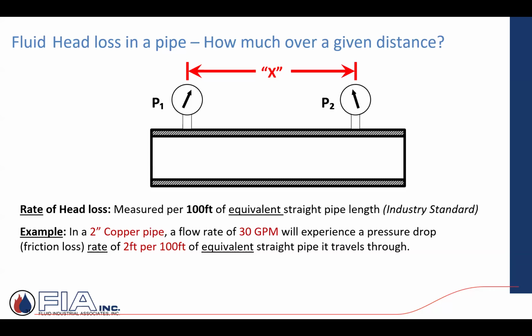So as a quick example, say I have a 2-inch copper pipe and a flow rate of 30 gallons a minute. When I look it up in software, whatever tool I'm using, that's going to experience a pressure drop, a friction loss rate, of 2 feet per 100 feet of equivalent straight pipe. So 30 gallons a minute, I got 500 feet of piping, TEL. That's telling me I would need a pump that can develop 10 feet of pressure differential to move that 30 GPM through 500 feet of piping. Because for 100 feet, it's going to experience this 2 feet. So 500 feet, just 5 times 2, I need 10 feet of head for that pump to develop to overcome the friction resistance.